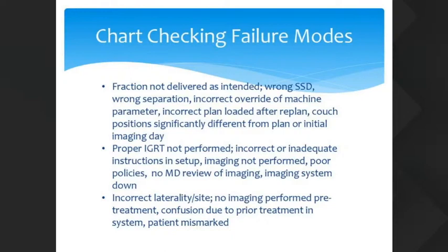Basically, there's no real correct answers here. It's based on your process in your individual clinic. And it's based on this graduated scale from 1 to 10 for each one of these three factors, O, S, and D. And when you have a group together, each member of the group would score the FMEA cause combinations, average them, and calculate the RPN number.